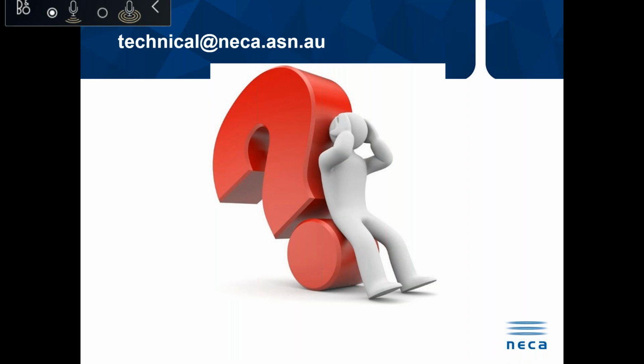Great, okay. And another question that's come through, why can I only use a 16 amp circuit breaker on a power circuit? If you have a look in the wiring rules, all domestic installations are deemed to have thermal insulation inside the wall, whether it's installed or not. There is a possibility that a government organisation may fund an insulation scheme to put insulation in walls to help build up the star rating of properties. So the cables have to be rated for this further possible installation of thermal insulation.